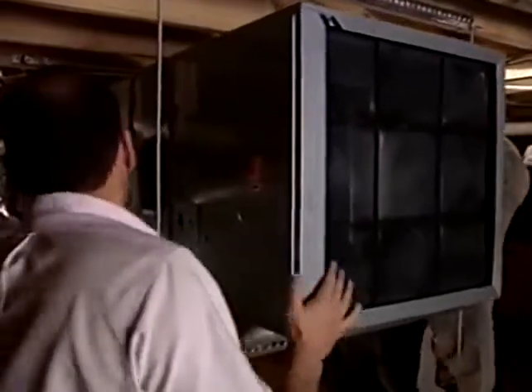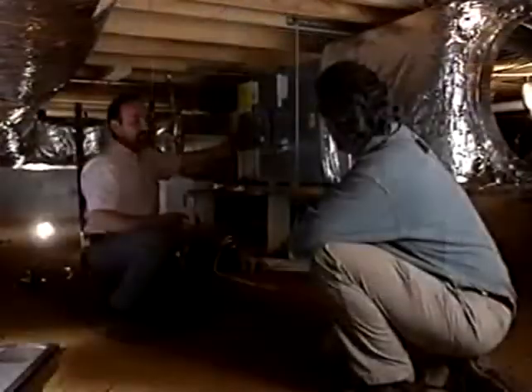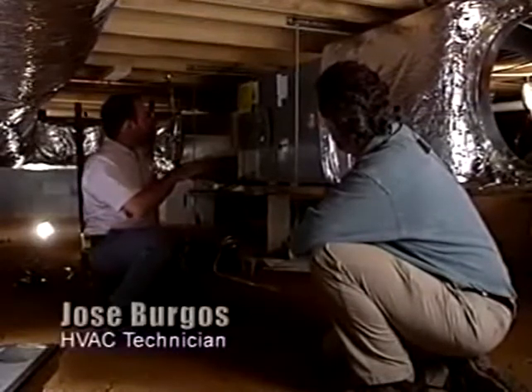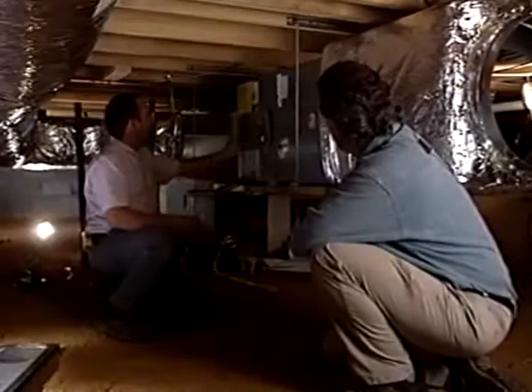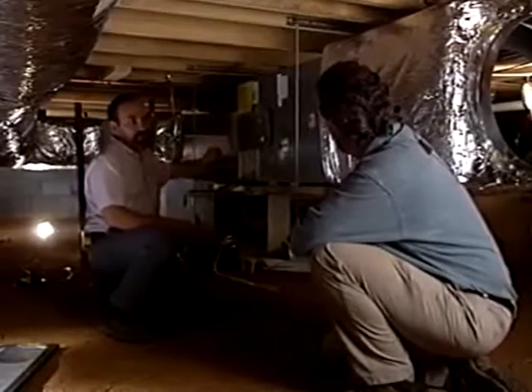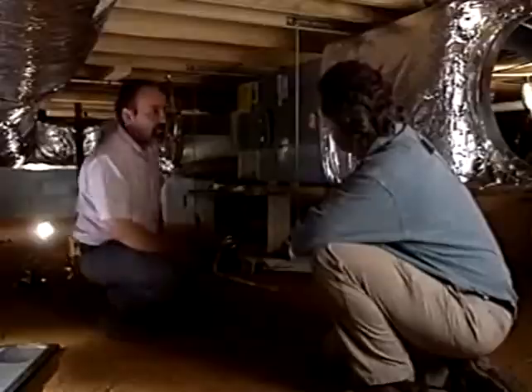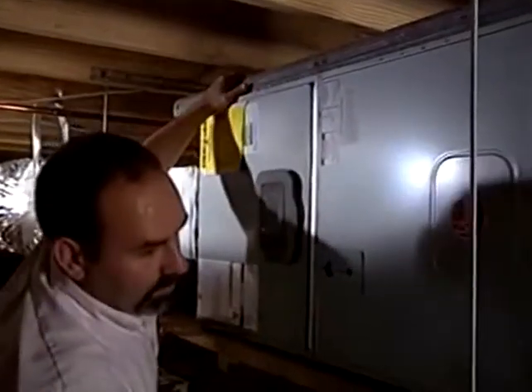We don't connect the air handler directly to the metal supply trunk. We use a flexible connector, which keeps any movement or vibration from the air handler passing to that metal deck and going to the floor of the house. Leveling the unit is also extremely important to the operation of the equipment. It helps to ensure the condensation lines drain away from the unit. Check your levels at all points to make sure the unit is level and secure. Finally, this contractor installs rubber pads on the bottom of the unit to help absorb vibrations.